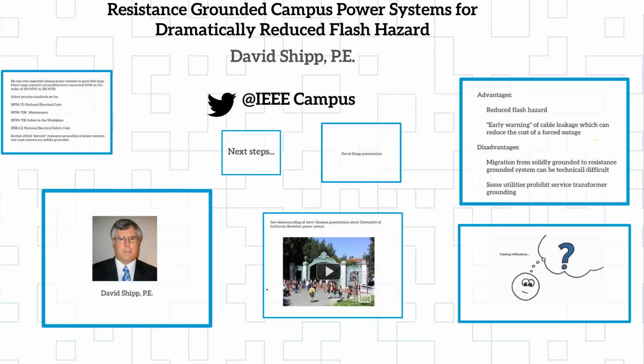the incident energy to do damage level is a mere fraction of what it is. The economic cost, the reliability, how long it takes to get you back in service, the cost to the university, or anybody. 15 kV cable today is about $75 per foot to replace. So if I burn the shields up in the cable at 15 kV and smoke 500 feet of cable, that's a big chunk of replacement money. If I clear it very quickly and limit the energy to something much smaller, and I'm just going to the equipment cost now, I'm not looking at the people safety piece of it yet, you can dramatically reduce it.